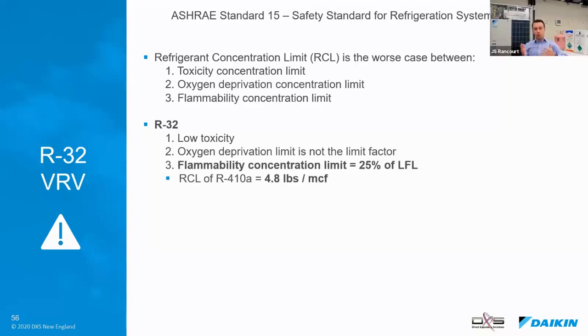So one of the rules with the new ASHRAE 15/2019 is, if it is an A2L refrigerant, we're gonna take the lower flammability limit, which is the minimum concentration you need for a flame to sustain. We're gonna divide it by 4, the safety factor of 4, and that becomes our maximum refrigerant concentration limit. So that means that R32's RCL, that 26 pounds for R410A, is now 4.8 pounds.